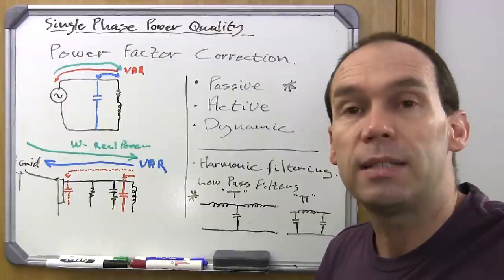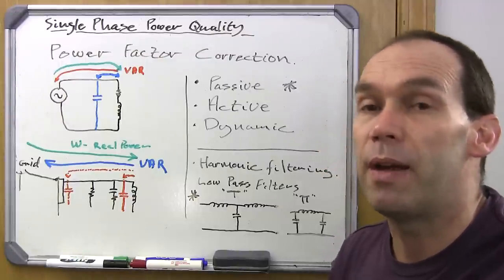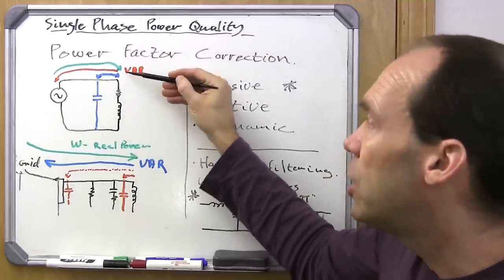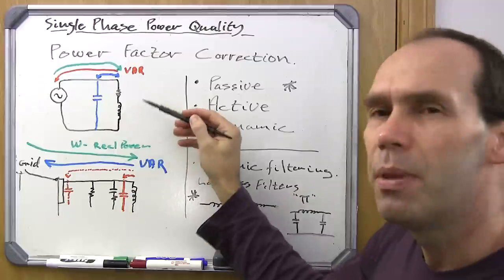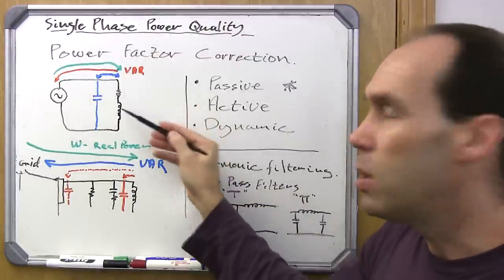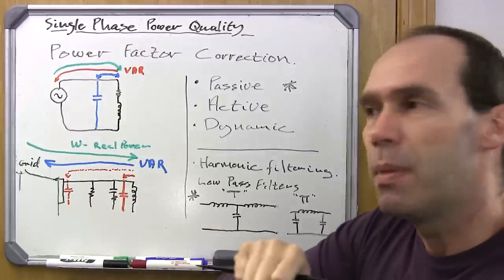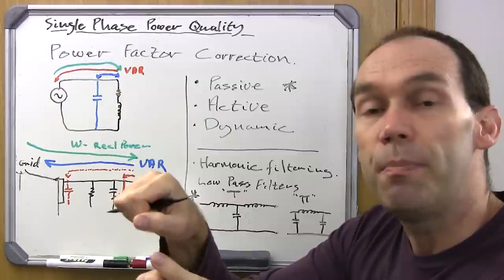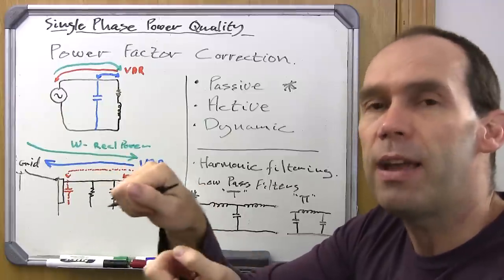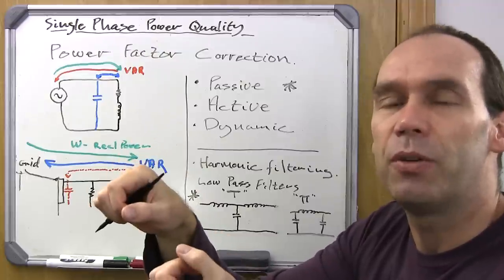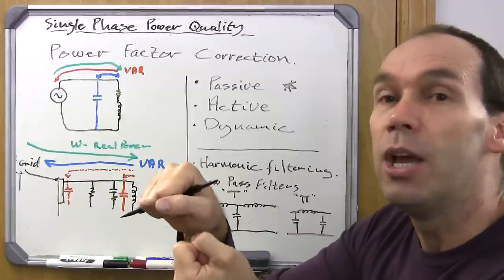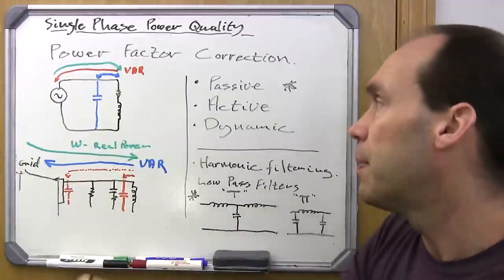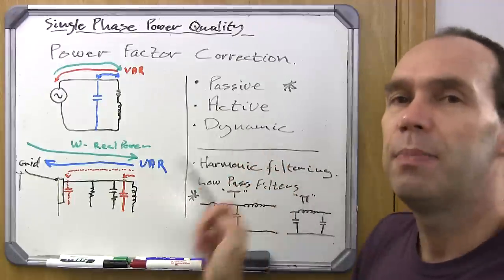For that inductive load I need about 7.5 microfarads, and that would be passive because it's a single component that isn't going to change — suitable for a static load. But if this motor varies, if it's pulling a varying load, that will change the dynamics of the power draw and phase. With a static power factor correction component in place, your power factor will go out. It will certainly help, but things will drift, and that's where we move to active power correction.